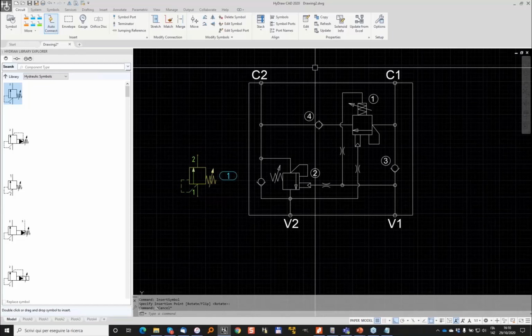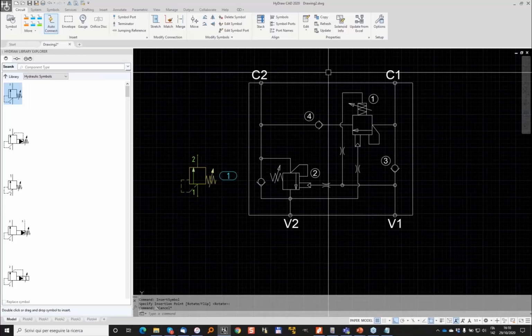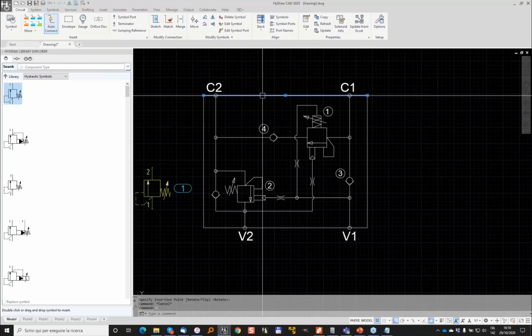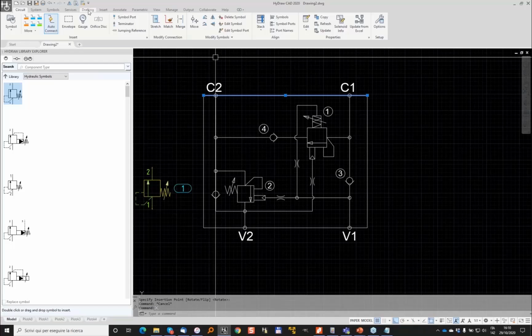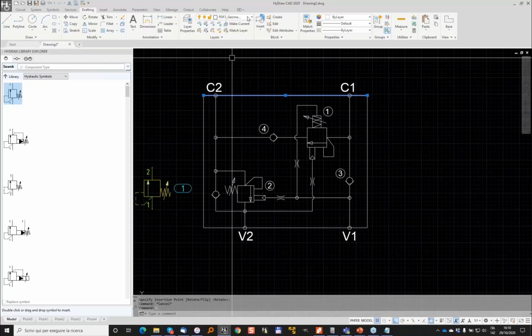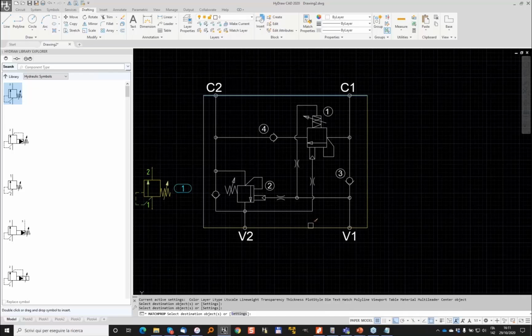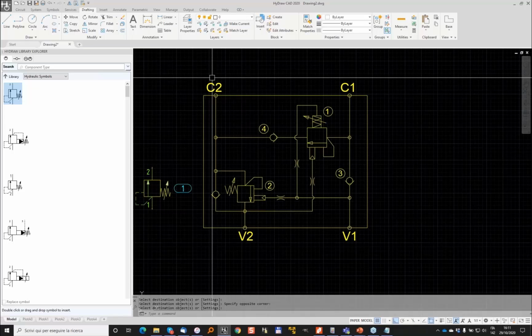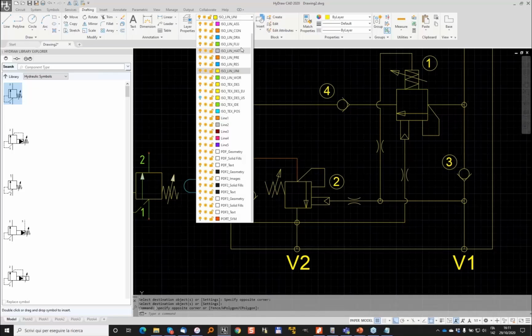So to arrange color in our diagram, we must be a bit familiar with the ISO standard if we want to make all the symbols compliant to ISO. And to change colors, well, ISO is also defining layers for all the symbols and all the drawing entities. So you move to the drafting. Normally boundaries are in the layer that is called ISO Line Uni. And you can use the match properties to copy attributes between different entities in the drawing. And let's say that I take everything yellow. The internal part, so the flow path in a symbol, should be using the ISO Line FLU.